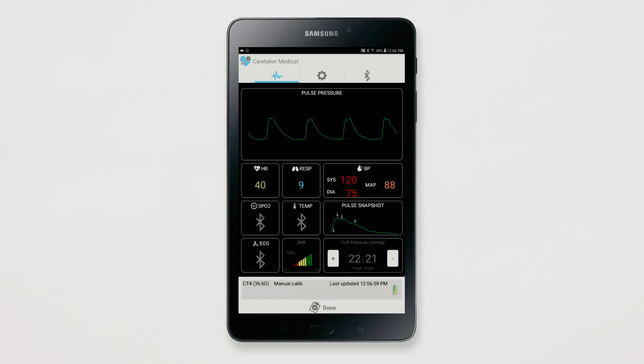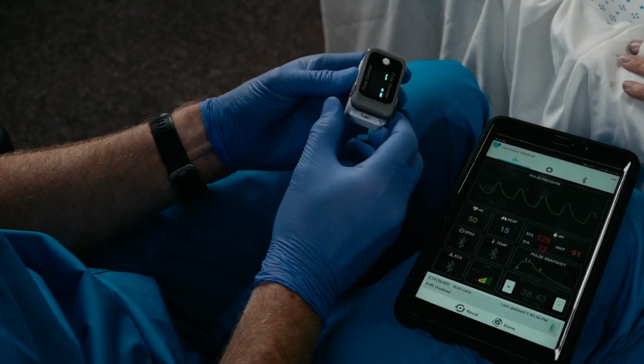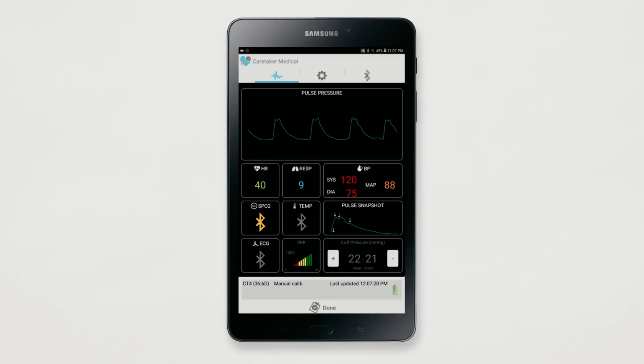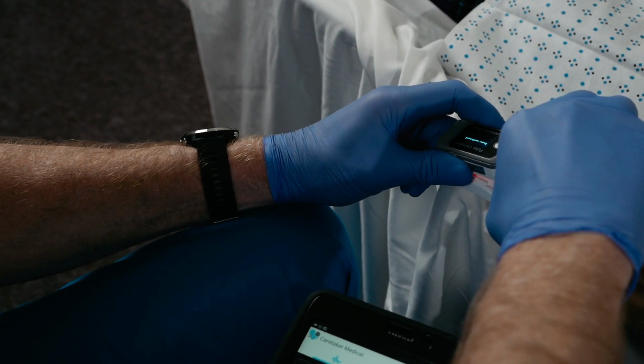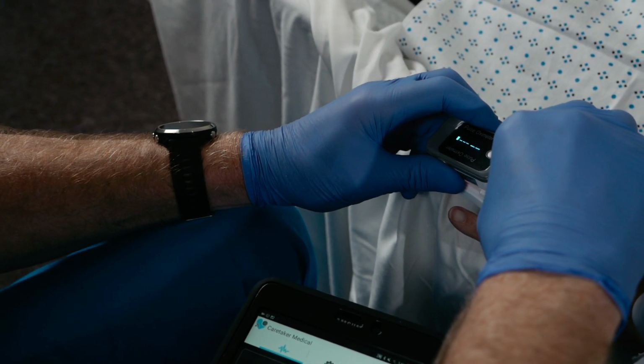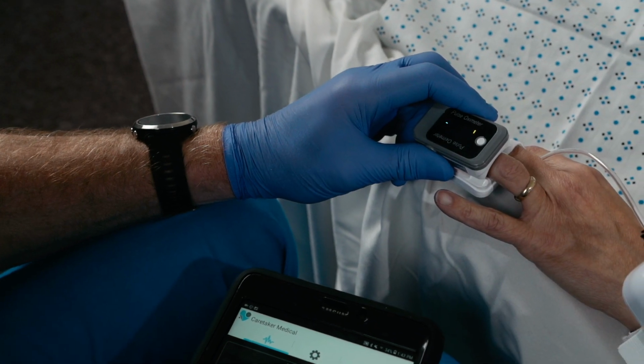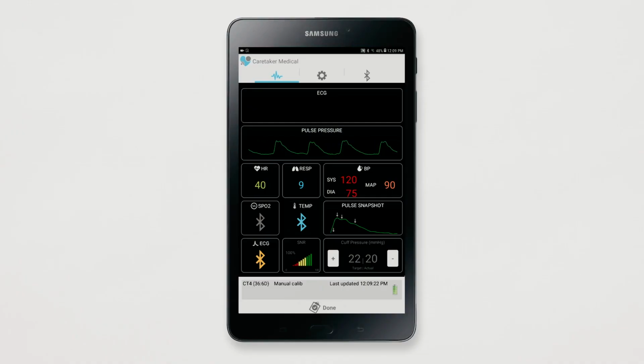To connect the other Bluetooth devices, simply long press on the device name. For example, to connect the pulse oximeter, long press on the SpO2 block and note the icon will turn orange. Turn on the pulse oximeter. The Bluetooth icon will now turn blue to show the connection has been made. The same method may be used to connect the optional temperature patch or ECG patch. To disconnect one of the Bluetooth devices, simply long press on the device name again.